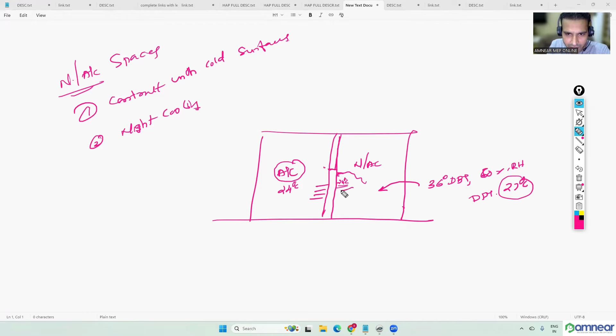Okay. See, since this room is having AC, we might be using a temperature of 24 degrees Celsius. And this is a partition wall. So this partition wall is exposed to the building surface. So if the partition wall is not a thermally perfectly insulated wall, what will happen? Due to conduction, the heat will be transferring to the other side. So eventually the other side also, the temperature will be reaching somewhat near to 24 degrees Celsius. Correct? So the inside air is having a dew point temperature of 27 degrees Celsius, but due to the presence of the nearest air conditioned space, due to conduction, this wall now has a temperature of 24. So now this hot air is having contact with these cold surfaces. What will happen? Condensation can come. Correct?